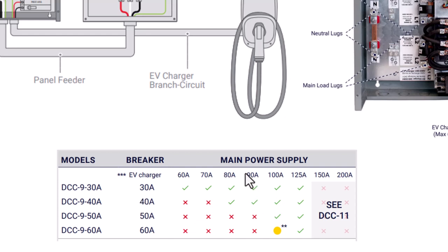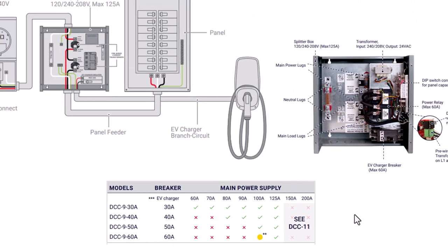So you could see that the higher the power supply, it's all allowed, as you can see here. But at the lowest, it's going to be 50%. So here, 50% of 60 would be 30. Same with 100. And with this one, they use a 125 because I believe a 120 is not a standard size. So they go with 125. So the 60 would work in that case.